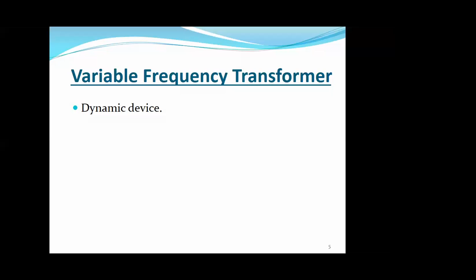So a variable frequency transformer is a dynamic device, just like an induction machine. In an induction machine, the rotor is rotating, so it is a dynamic device. It is basically a doubly fed wound rotor induction machine, as I told you earlier. Since frequencies at both sides are different, it can be used for connecting asynchronous power system networks.